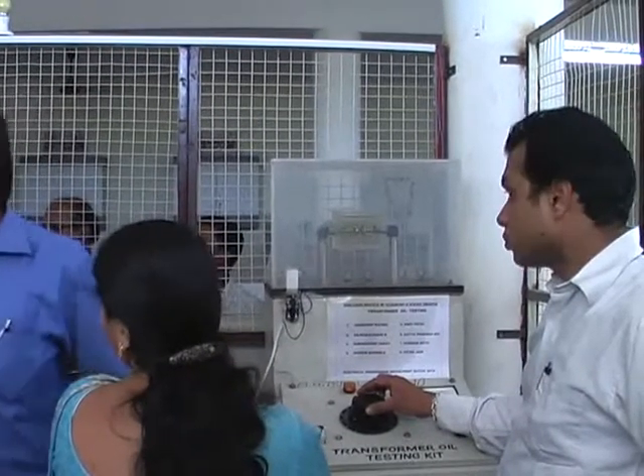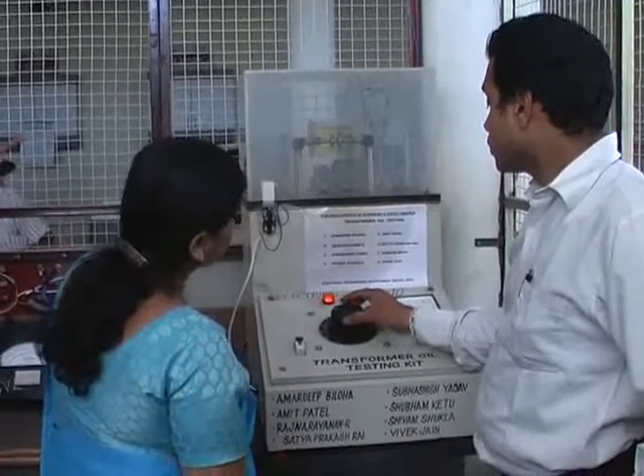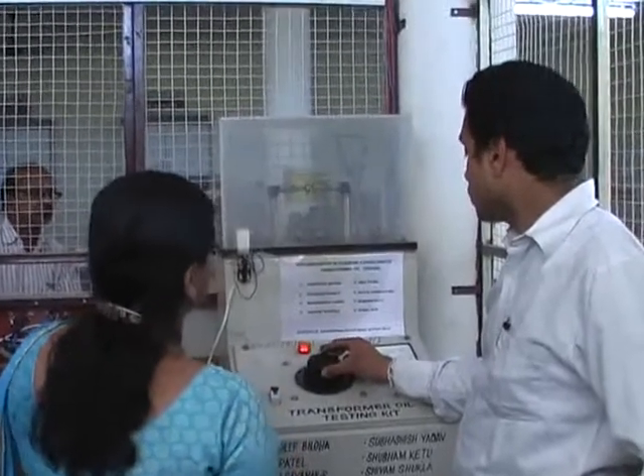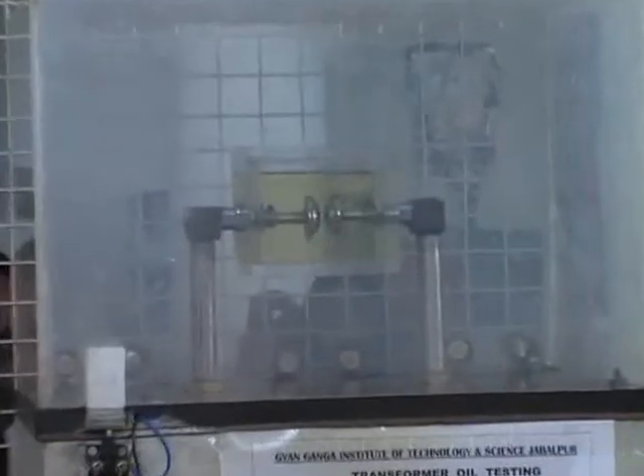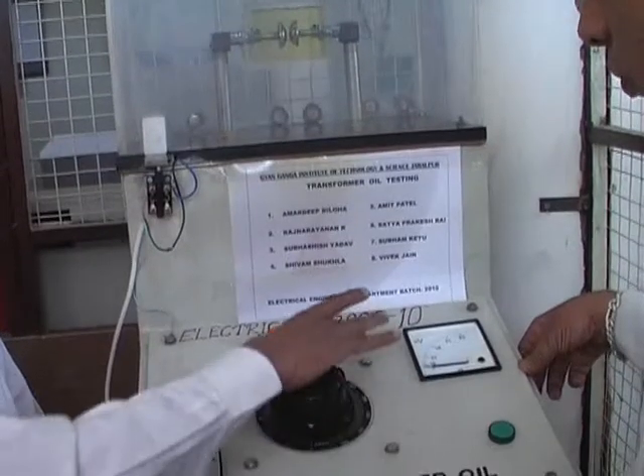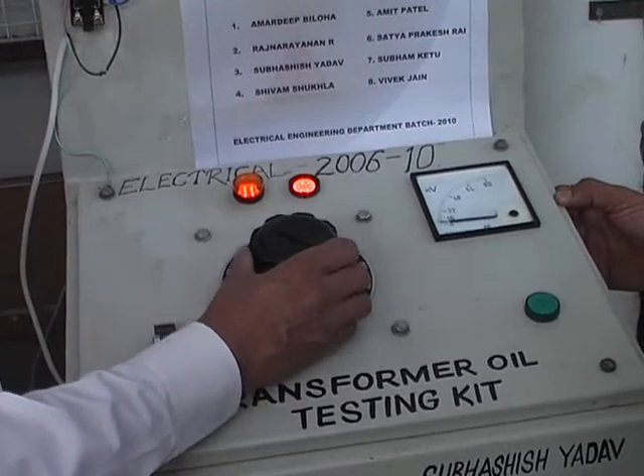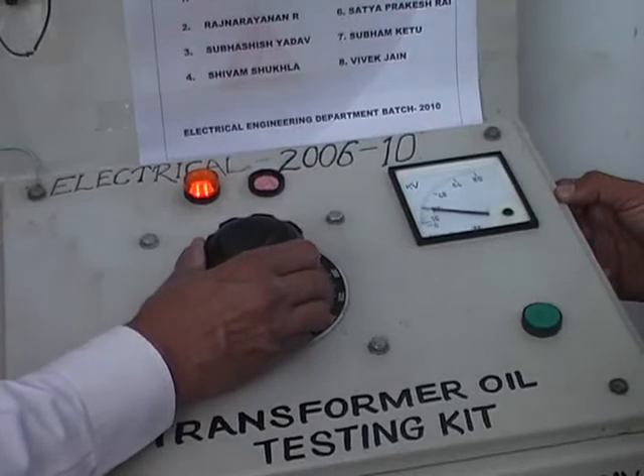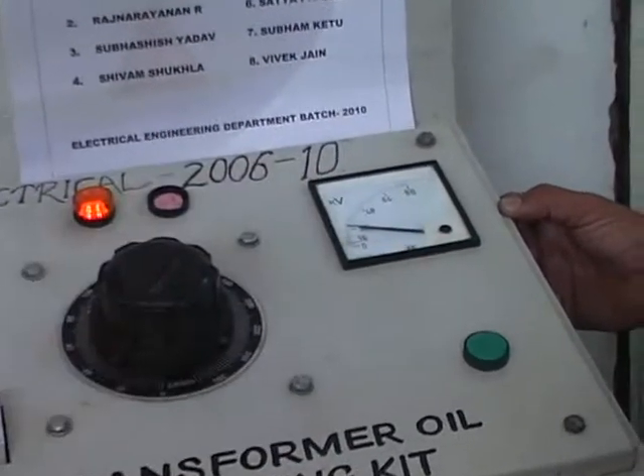The gap between the two spheres is kept as 2.5 mm as per IS requirement, and the voltage developed by the kit is gradually, at a constant rate, increased to give a spark. No sooner the spark is there, the test setup comes to a standstill, and the voltage at which spark has taken over is captured by the voltmeter. In this case, transformer oil under test has given a breakdown voltage of around 34 kV. The oil which has been tested was taken out from the transformer in service.